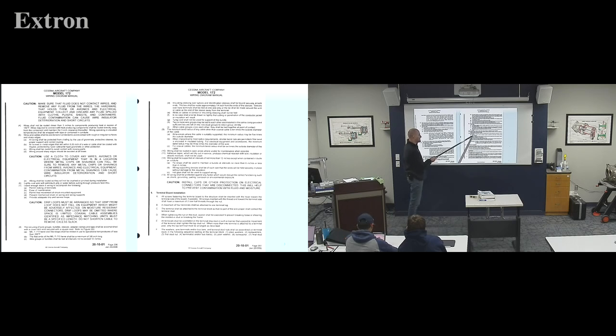Tie wraps shall be used to maintain a bundle at intervals. Wait, what? So actually tie wraps, but no more than 6 inches or less than 4 inches. So they want you maintaining, the way they use the word, maintaining the bundle so that it's not crazy hair. Corbin knows what that's like, right? You got maintained into a nice ponytail or out like crazy. So they actually tell you, yeah, go ahead and maintain your bundles, but they go a little bit further. They go, well, lacing would be the same idea, but you have to look if they spell it out.